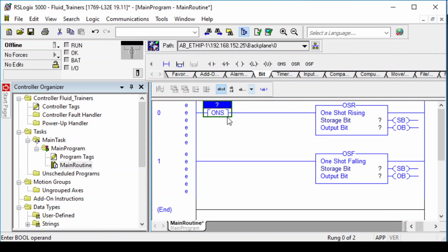In Allen Bradley world, this checks all of the inputs before it. So if you have two sensor inputs, both have to be true before that one shot will trigger. Which is kind of nice because then the order doesn't matter. If I had a start button and a limit switch, if the limit switch triggered first, then the start button, the one shot would trigger. If the start button was first, then the limit switch, it would still trigger. Again, in Siemens world, if the start button was false and then the limit tripped and then the start button was pressed, the output would have missed that one shot from the limit switch being pressed already, so we wouldn't have done anything. So both do have their benefit, is really what it comes down to.